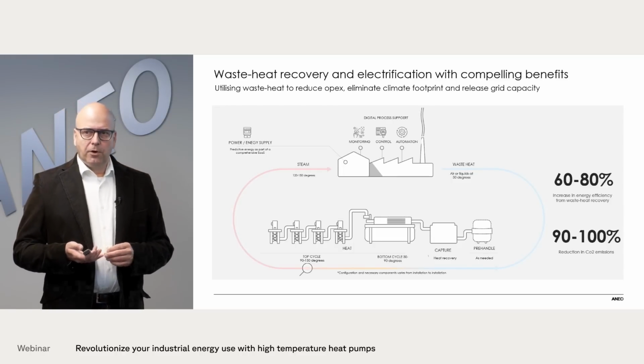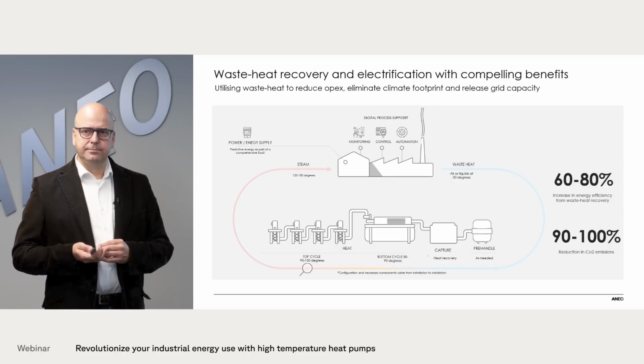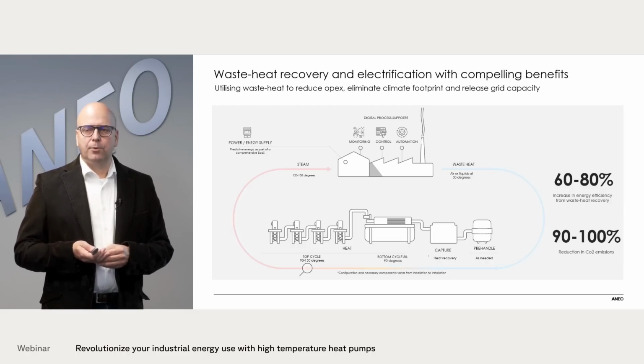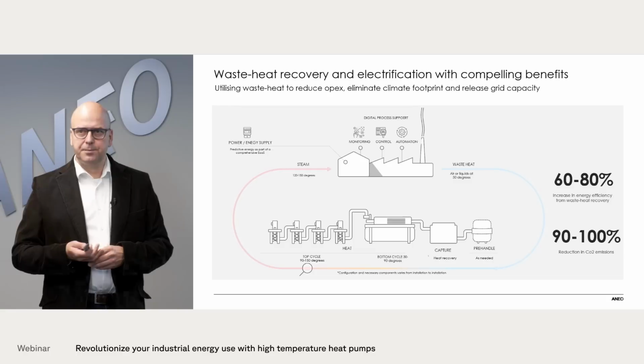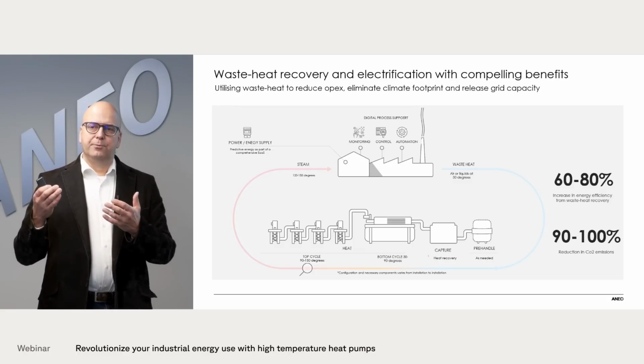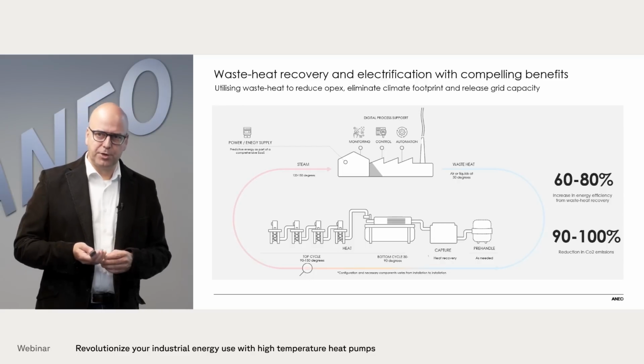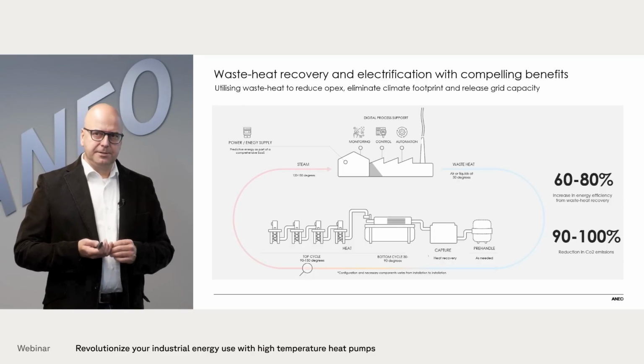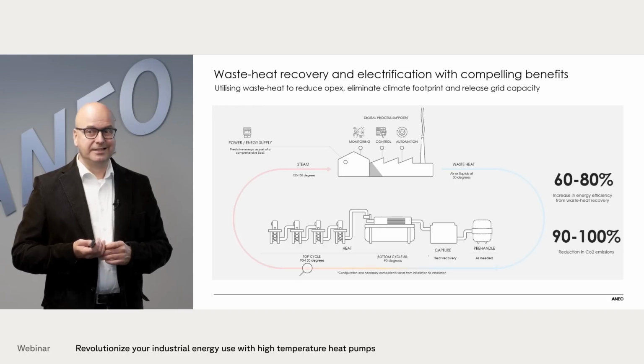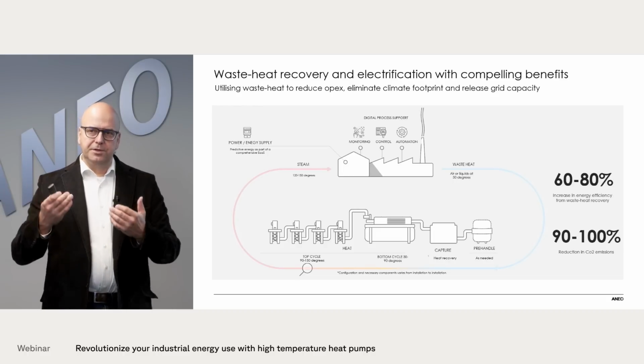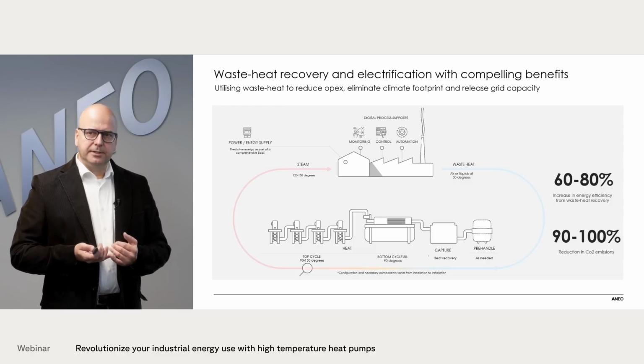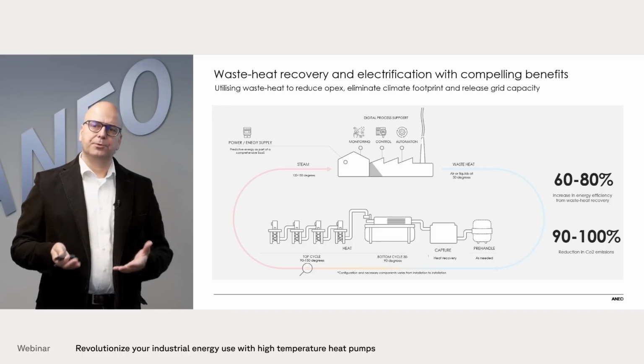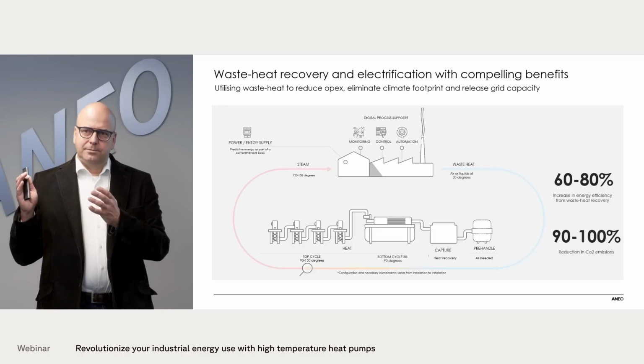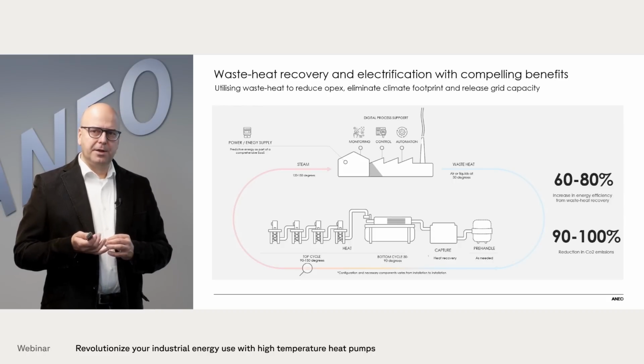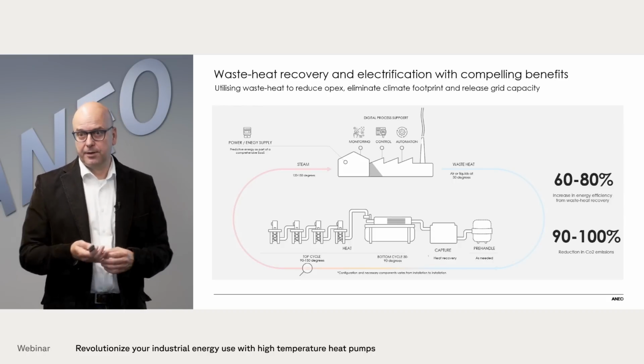So what do we do? As we saw, we basically have two heat pump technologies in our system. But in order to get this running and integrated into the factory, it's important that we also have a unit, what we call the energy recovery unit, which takes the waste heat from the factory, recovers it and brings it to the heat pump. So this is basically a heat exchanger. In the case we have presented, the heat exchanger is designed and operated with moist and dusty air. We have to cool this air down, and we recover the waste heat in this heat exchanger and transport it to a water cycle. The main challenge of the heat exchanger here is not so much to recover the energy, but to handle real industrial conditions, especially the dust.